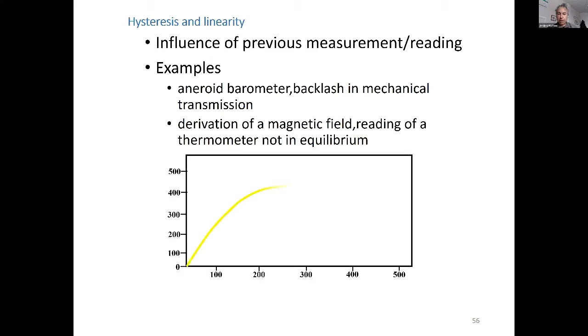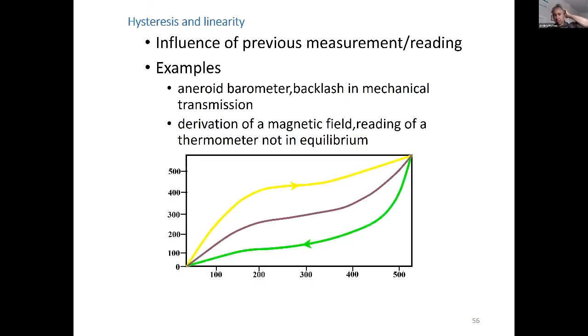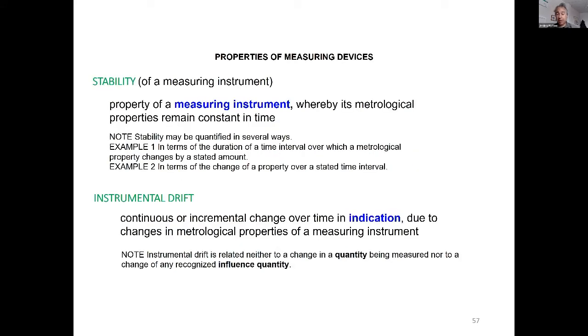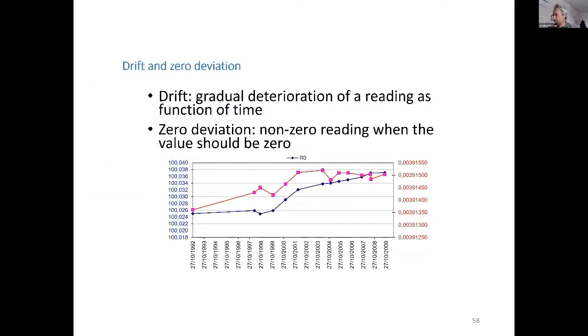Hysteresis, there are ways to measure the hysteresis. It affects temperature, pressure, and so on. Again, I don't go very much into this. Stability and drift, we have seen all of them yesterday. So this is why I told you today I will go a little bit in a hurry. The drift is something that we need to check, especially in such kind of environment where instruments are not used to being exposed and when environmental forcing may change something.